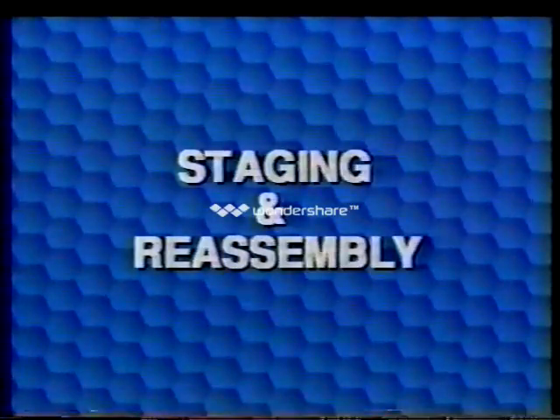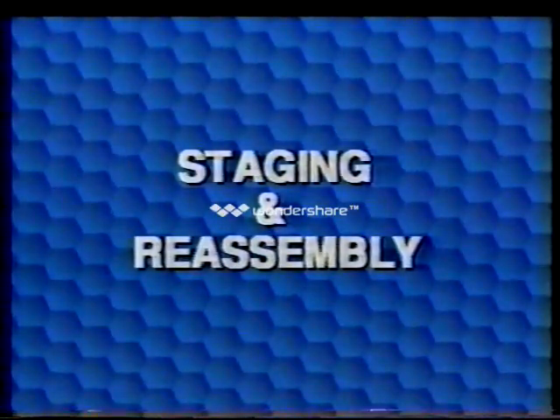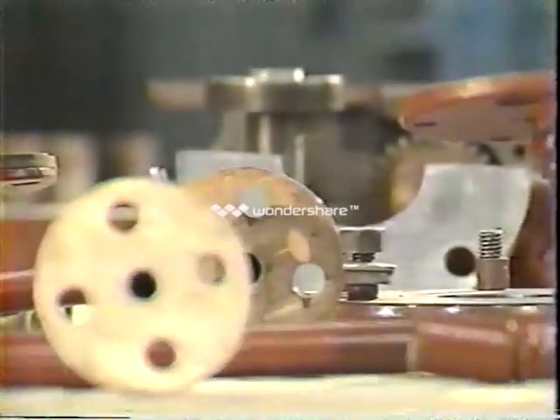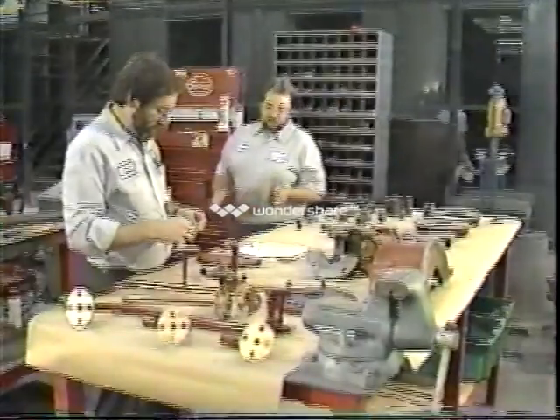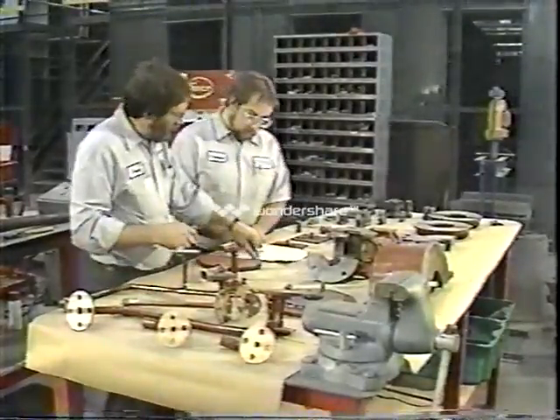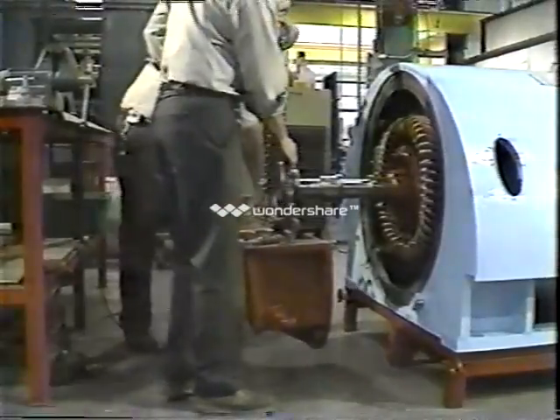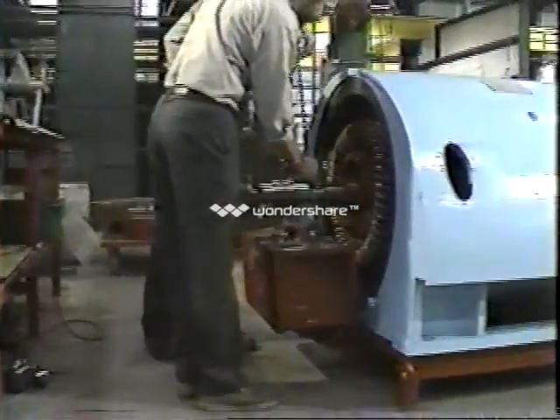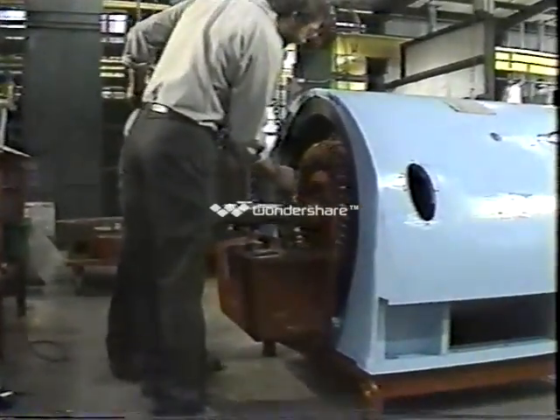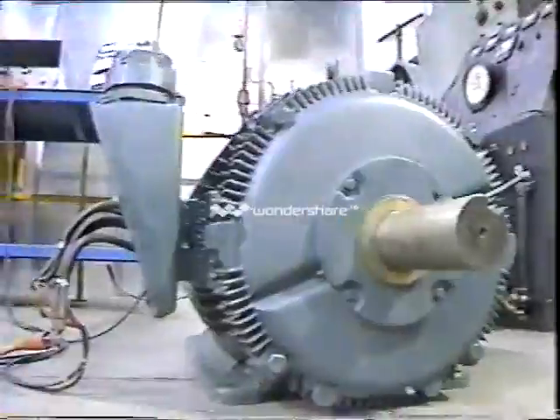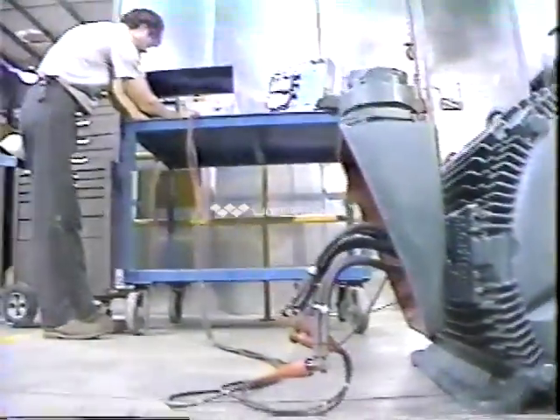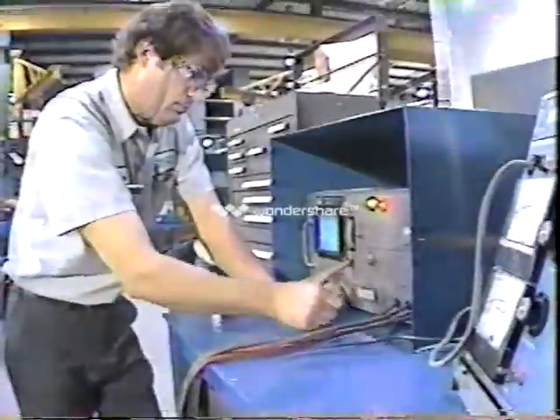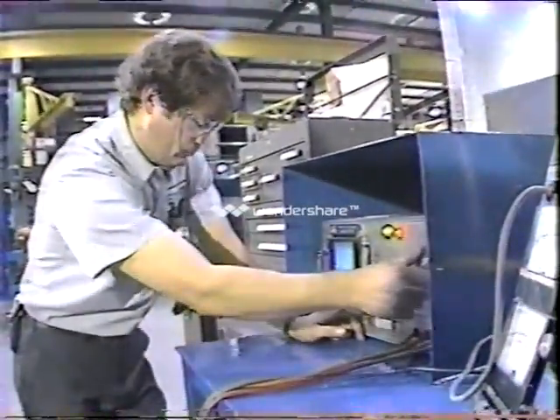Once the stator and rotor have been reworked, we then go through the process of staging. Now this is where we set out every part that is to be reassembled, make sure that our parts list is complete and that each part is cleaned and inspected thoroughly. Then each part of the motor is reassembled, resulting in a motor that meets the most demanding industry standards. But that's not all. At Ingleside Electric, we feel that perhaps the most important part of our job is testing. We perform many different tests on each motor that we reassemble. Before we ever apply voltage, we make sure that the new winding passes the Baker's surge comparison, a test for shorts, open connections, and ground insulation integrity.